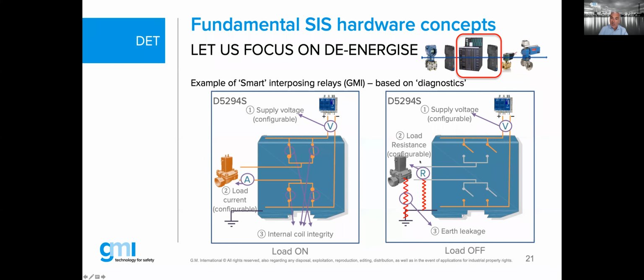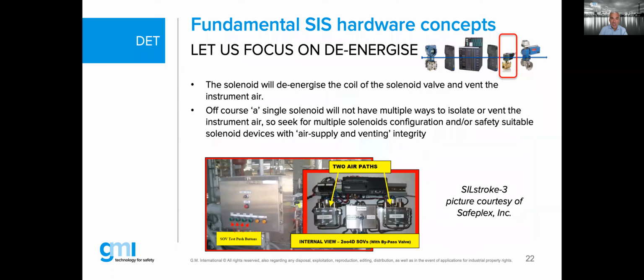Now, as you can see here on the right-hand side, even in case the relay here would be open, we also do a short circuit, or we also do an earth leakage monitoring, and that monitoring is what is fed back into our diagnostics. That is a relay based diagnostics example, which we show here, very simple with this schematic. Again, more details are available in the webinars of GMI.